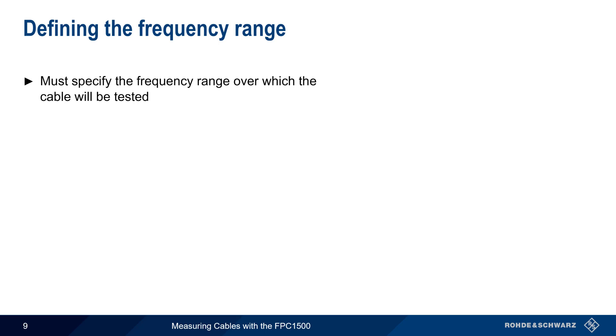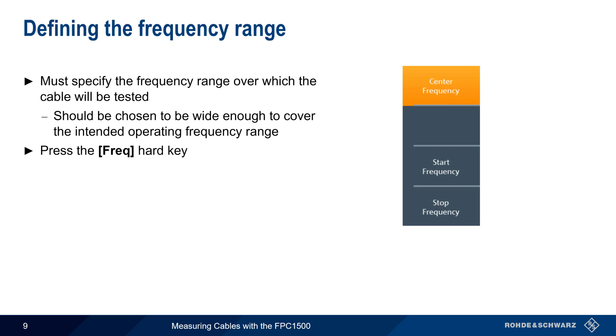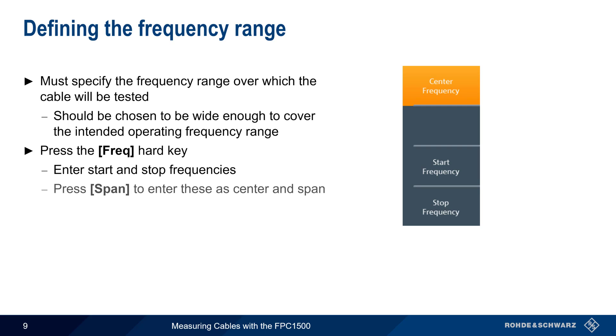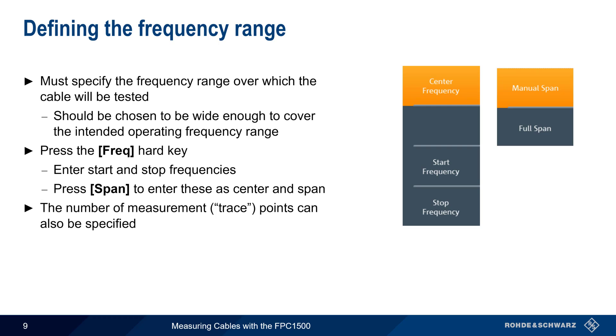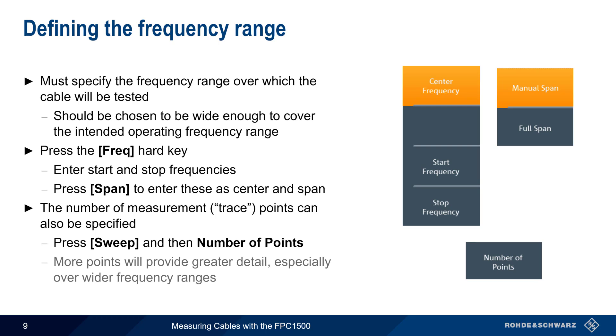We also need to specify the frequency range over which the cable will be tested. This should cover the intended operating frequency range. To define the frequency range, press the Frequency hard key and enter the Start and Stop frequencies. The Span key can also be used to enter these as Center and Span instead. The number of measurement or trace points over the span can also be specified by pressing the Sweep hard key and then adjusting the number of points. A greater number of points will provide greater detail, particularly over wide frequency ranges.